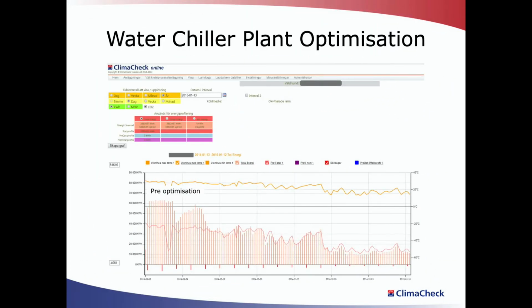The ClimaCheck web server is a very powerful tool. In this example, the water chiller shown is being optimized to increase its performance efficiency and thereby reduce its power consumption. Currently running at up to 65,000 kilowatt hours, optimization has enabled the power consumption to be reduced dramatically, and you can see the before and after effects in this graph.